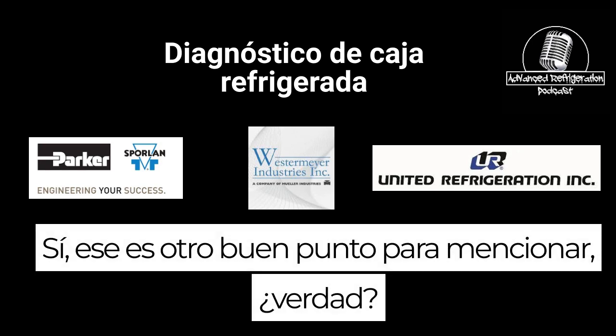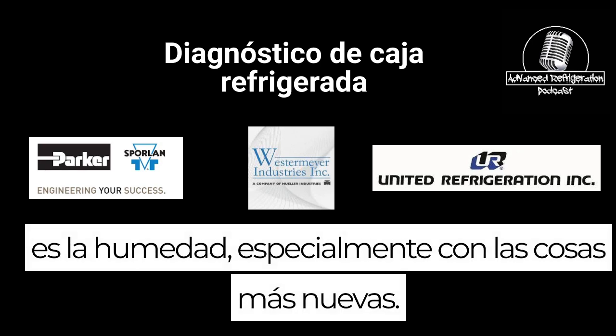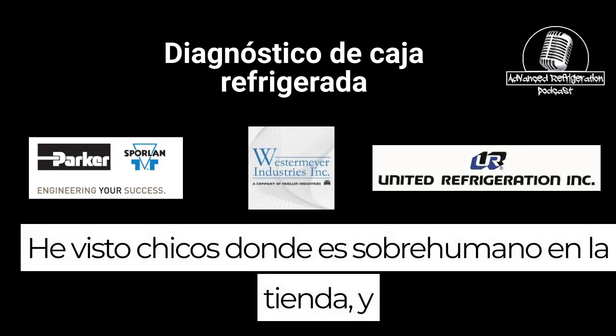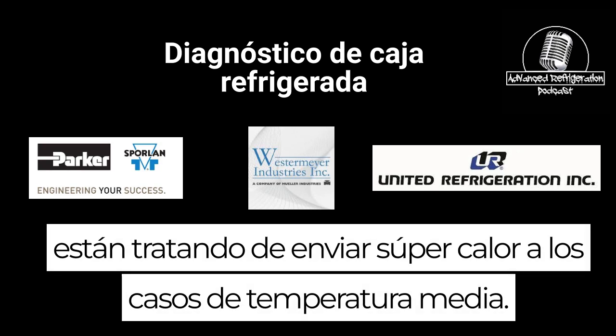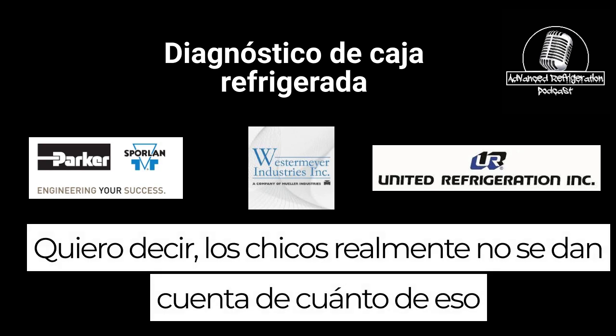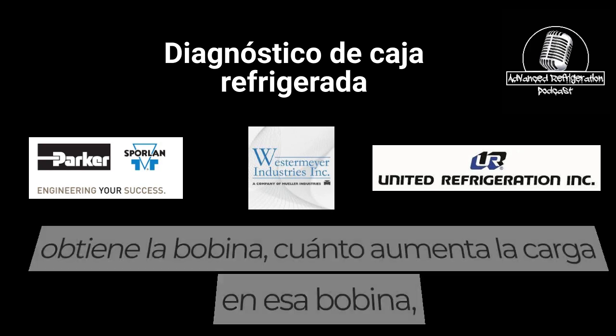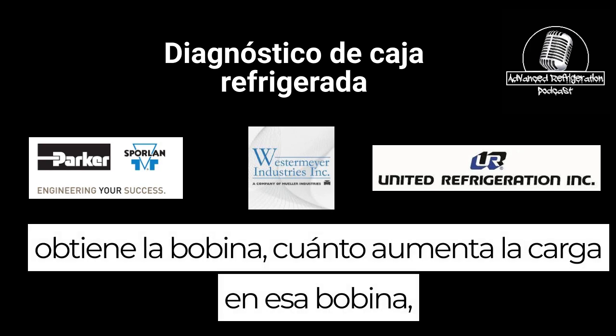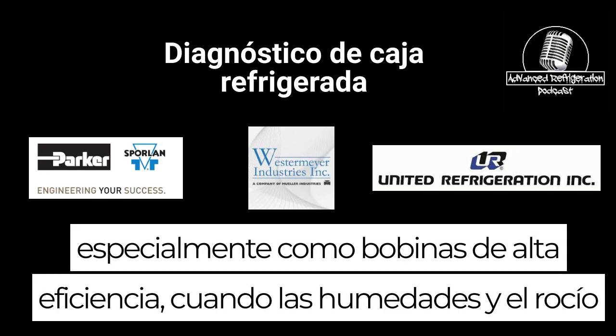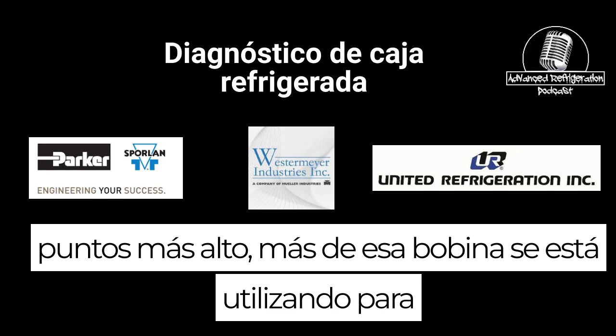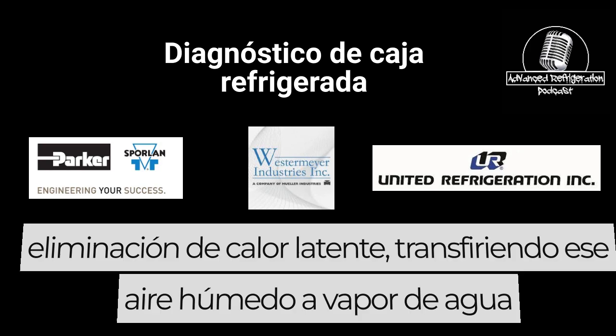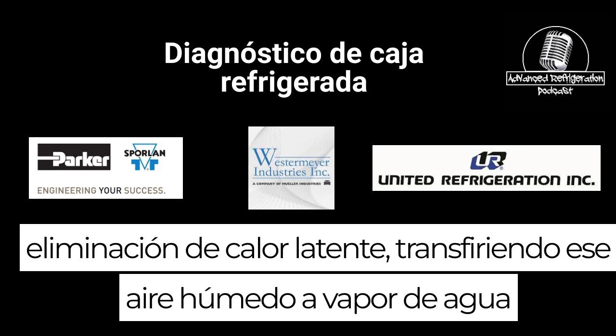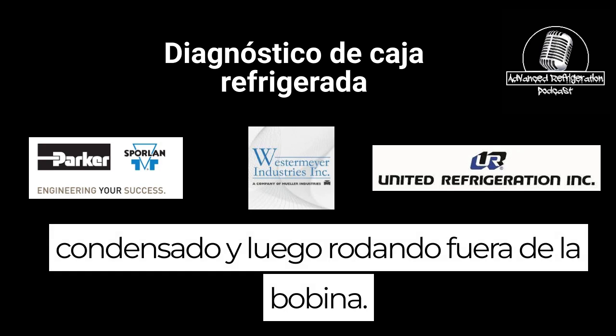Yeah, that's another good point to bring up, right, the humidity, especially with the newer stuff. I've seen guys where it's super humid in the store and they're trying to adjust superheat on medium temp cases. Guys don't really realize how much the load increases on that coil, especially high efficiency coils. When the humidity and dew point are higher, more of that coil is being used for latent heat removal, transferring that humid air into water vapor, condensate, and then rolling off the coil.